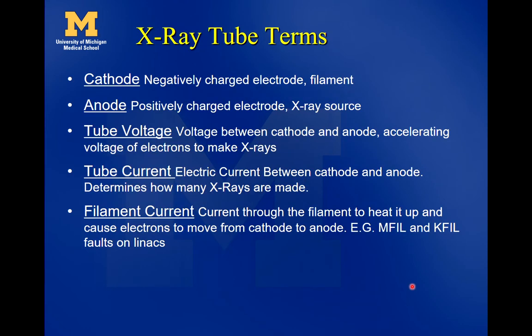Some terminology to memorize: the cathode is a negatively charged electrode — it's the filament, mostly made out of tungsten, with current going through it to make it very hot. The anode is the positively charged electrode where the electrons stop and where the x-ray source is created. The tube voltage is the voltage between the cathode and the anode — it's the accelerating voltage of the electrons to make x-rays, and it's the parameter we can tune by selecting the desired tube voltage.